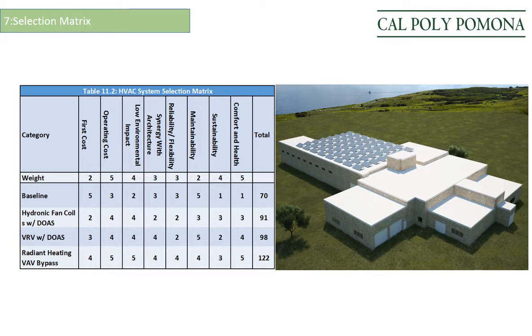Each system was then scored from a scale of 1 to 5, 5 meeting all category requirements, 1 meeting no category requirements. After scoring the selection matrix, radiant heating VAV bypass scored the highest with a score of 122. Next was VRV with dedicated outdoor system with score 98. Third was hydronic fan coil with dedicated outdoor system with a score of 91. And lastly was a baseline with a score of 70.